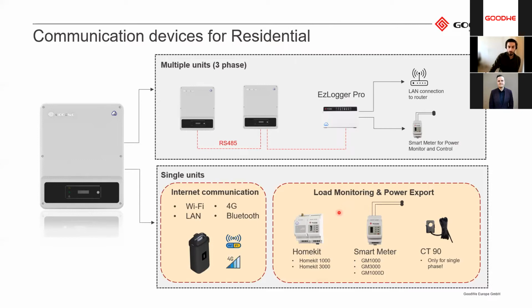If you do not care about monitoring the loads and just want to make sure that you do not export any excess power to the grid, then you can use this smart meter. There are a few different versions depending on whether it's a single-phase or three-phase inverter. For the XS and the DNS, you can also use the CT90s directly connected to the inverter, without needing to use the smart meter.